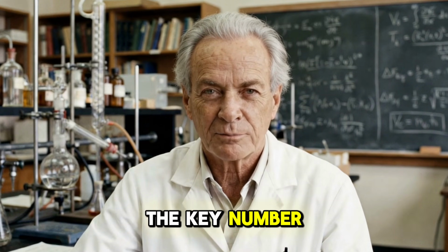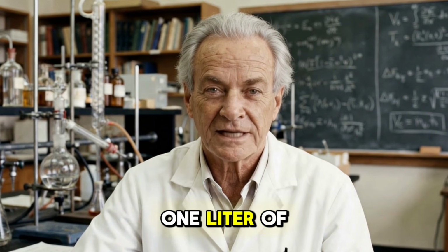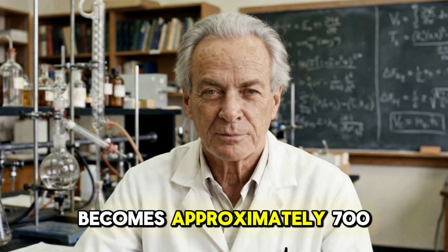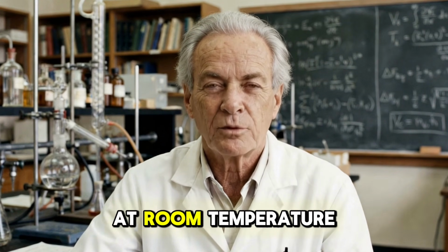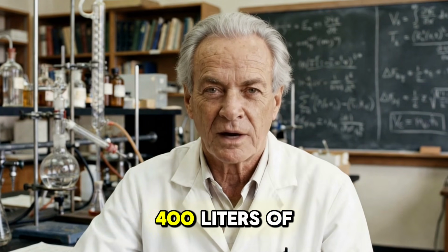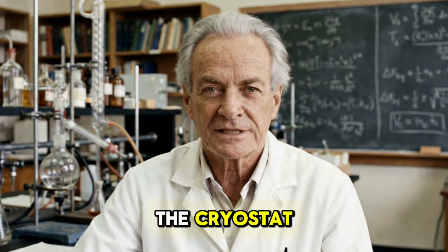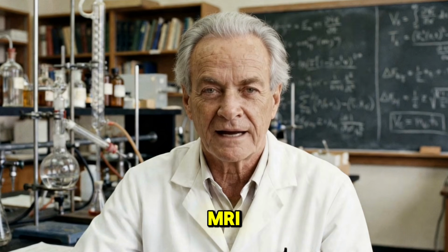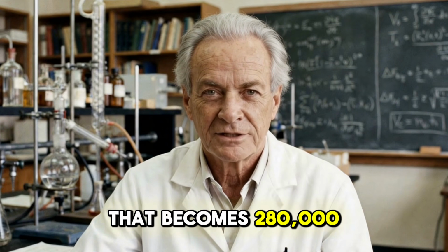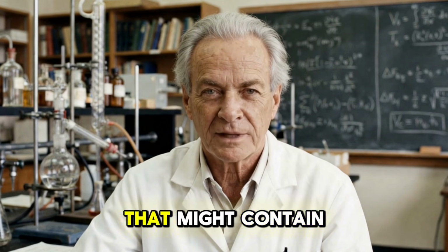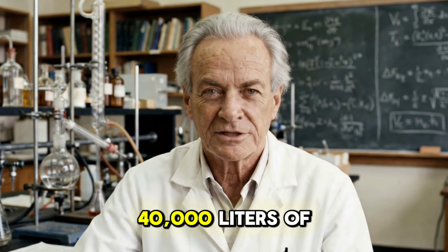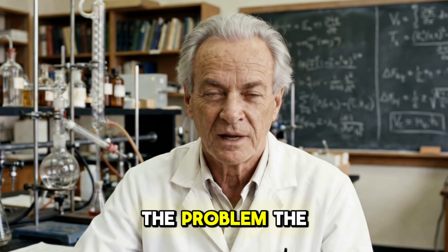And here is the key number you need to remember. 1 liter of liquid helium becomes approximately 700 liters of gas at room temperature. If you have 400 liters of liquid helium in the cryostat, which is typical for a clinical MRI, that becomes 280,000 liters of gas, in a room that might contain only 30 or 40,000 liters of air. Do you see the problem?